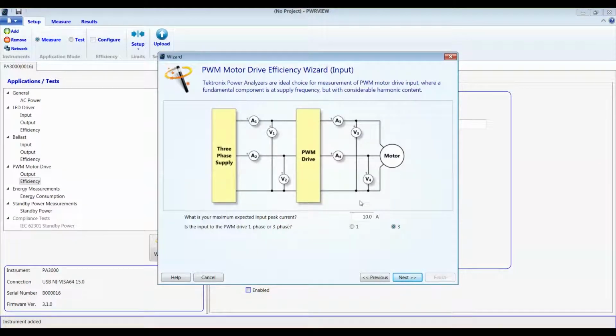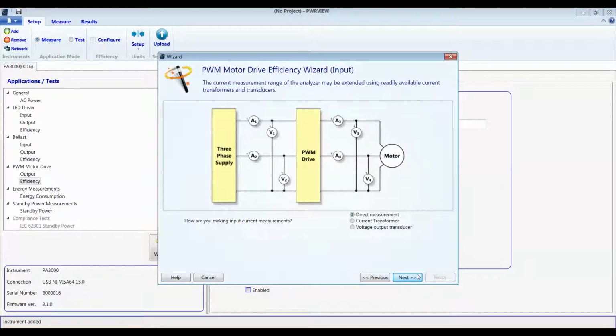Our expected input current is about 3 amps. Let's enter that and click next. We are using internal shunts in this case, as expected current is about 3 amps or so, much lower than the 30 amp shunt rating. So we'll keep the default selection of direct measurements and click next.